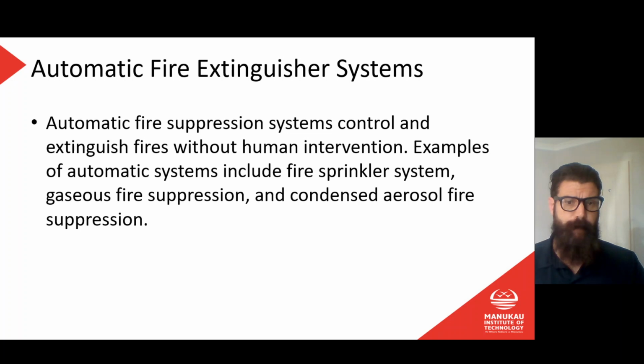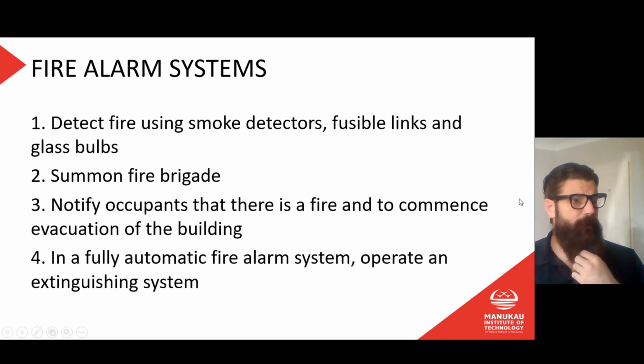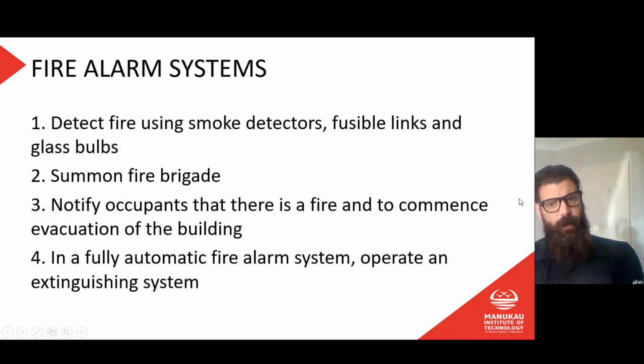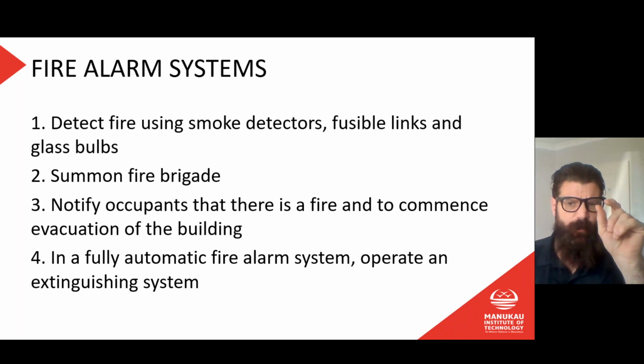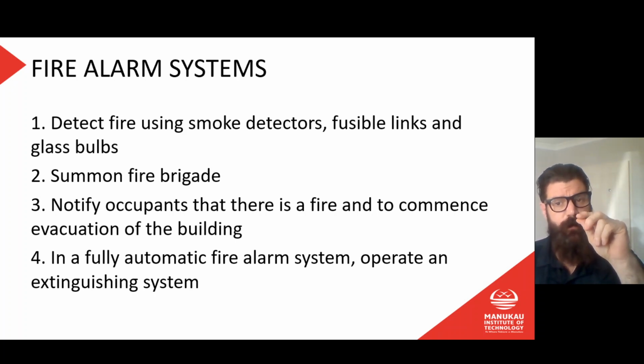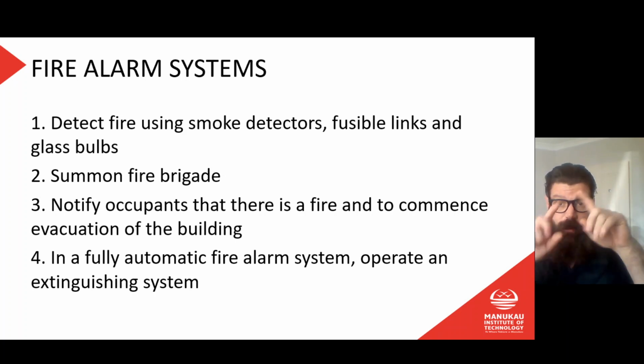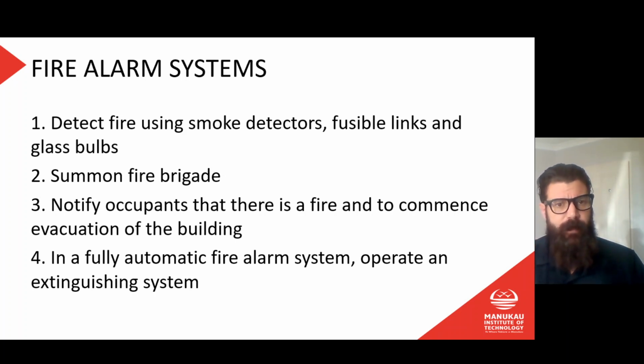Fire alarm systems. A fire alarm system will detect a fire using smoke detectors, fusible links, and glass bulbs. So a fusible link is a little bit of wire that will melt at a certain temperature, so that would open or close a circuit and send a signal back to the fire control panel. They will summon the fire brigade. They'll notify occupants that there's a fire and to commence evacuation of the building. In a fully automatic fire alarm system, they will operate an extinguishing system.